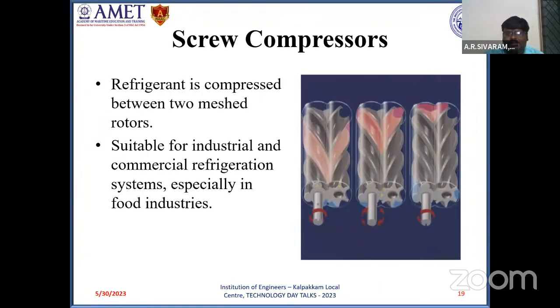Screw type compressors. Screw type compressors have 2 meshed rotors. Among the 2 meshed rotors, one rotor is connected to the motor present in the compressor. The motor powers the meshed rotor, and the refrigerant gets compressed between the 2 meshed rotors and leaves at comparatively high discharge pressure. This is more suitable for commercial and industrial refrigeration systems, and is mostly used in food industries.